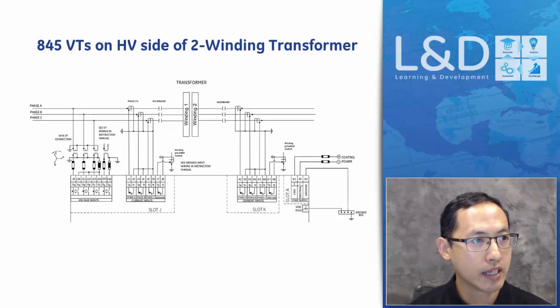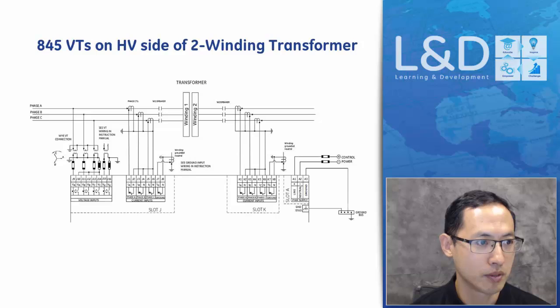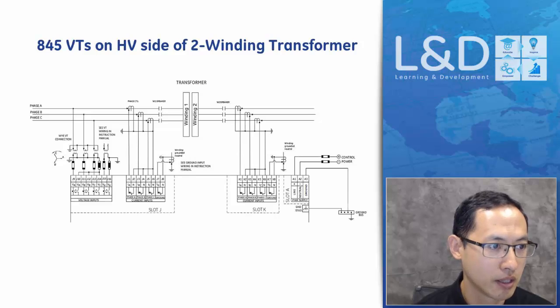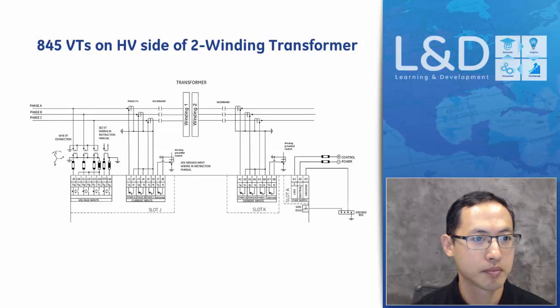For the 845 transformer relays, there are different types of configurations, depending on the order code. It can have 2 windings with VTs on the high and low side. So this is the diagram of the VTs on the high side of the transformer. It uses the J slot card, J9 to J16, for the VT inputs, and J1 for the CTs of the high side, and K1 for the CTs of the low side.